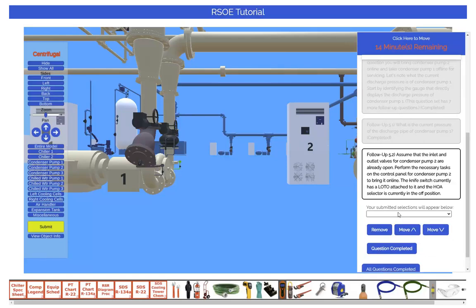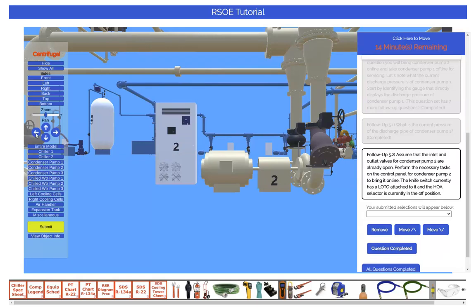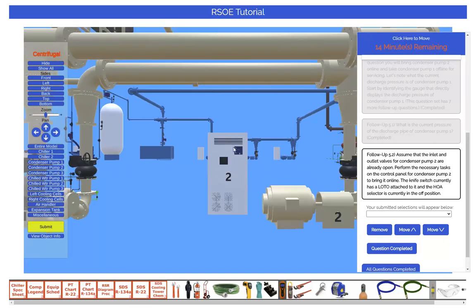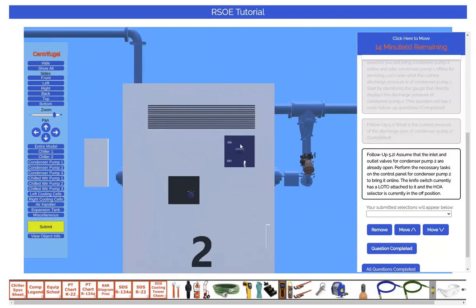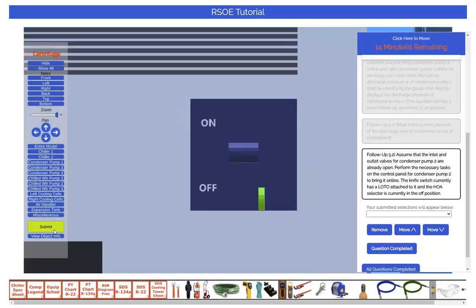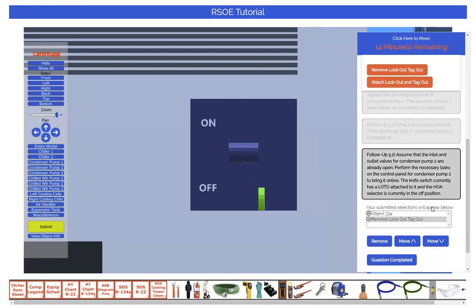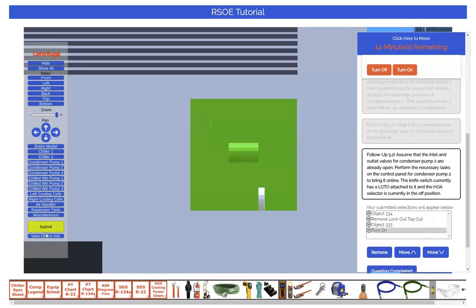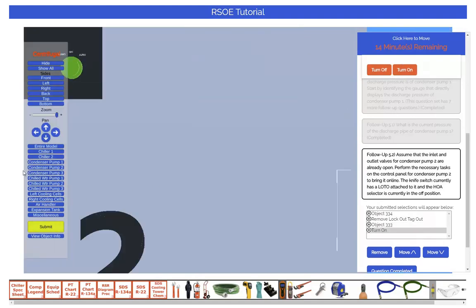This question tells us the current status of Condenser Pump 2 and that information tells us what we need to do next. First we will remove the lockout tagout from the knife switch. Next we will turn the knife switch on. Next we will turn the selector switch from off to auto. Doing so will start up Condenser Pump 2. This is everything that is required to answer this specific question, so let's complete the question.